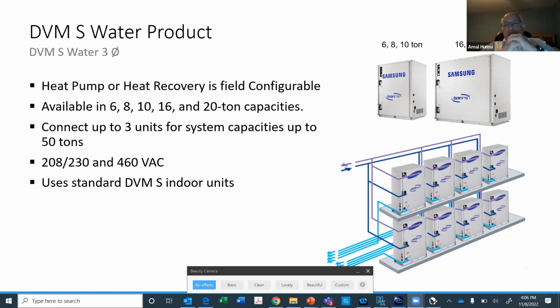It's the same unit, but you can configure it in the field to use it as a heat pump or a heat recovery unit. Heat recovery, which you might not be familiar with in the VRF world, means you can do simultaneous heating and cooling at the same time -- so you might have a space that requires cooling and another that requires heating, and with a heat recovery system you'll be able to do that.